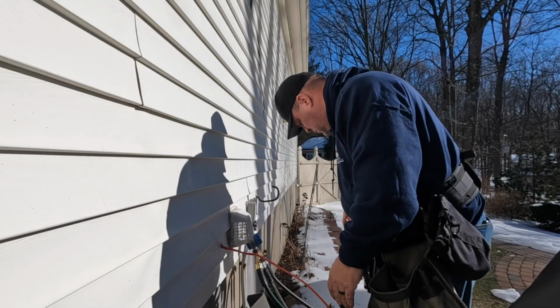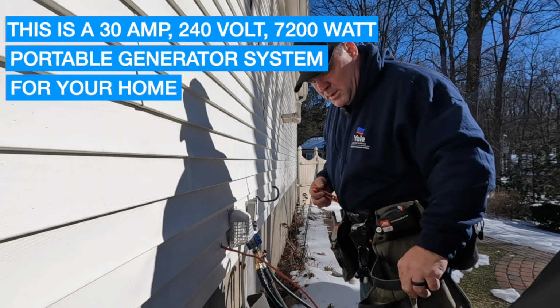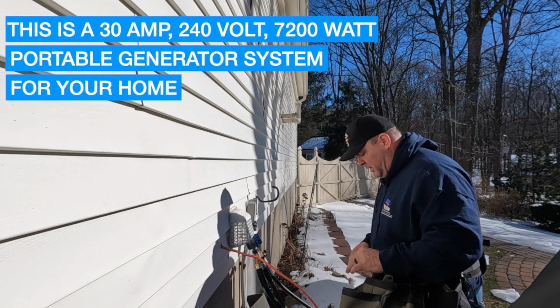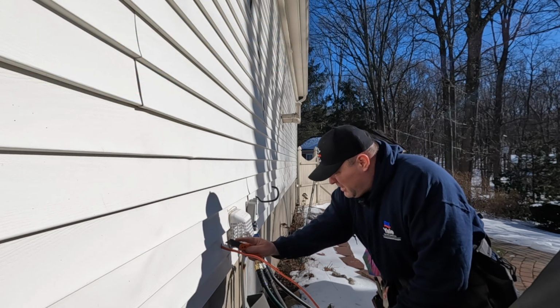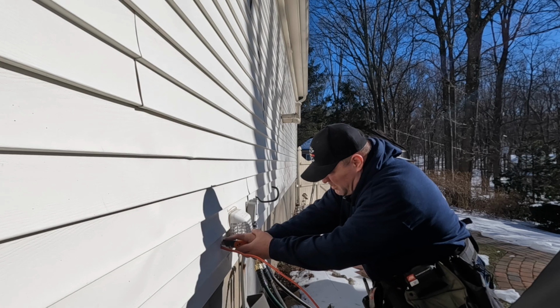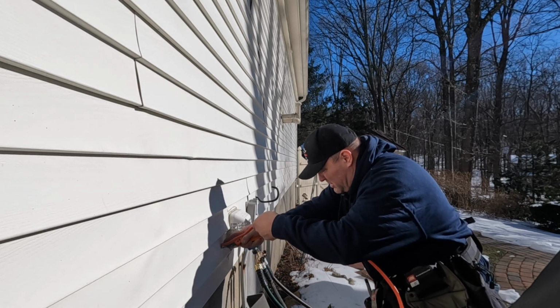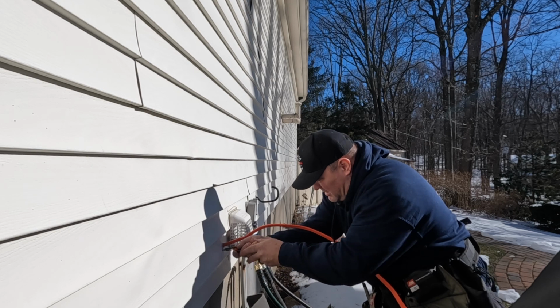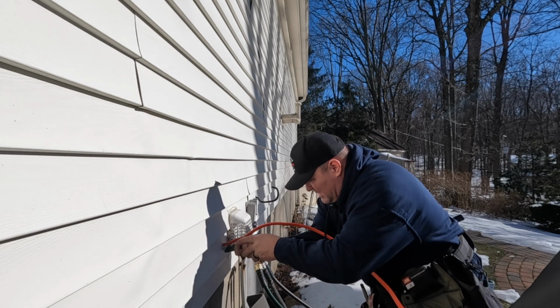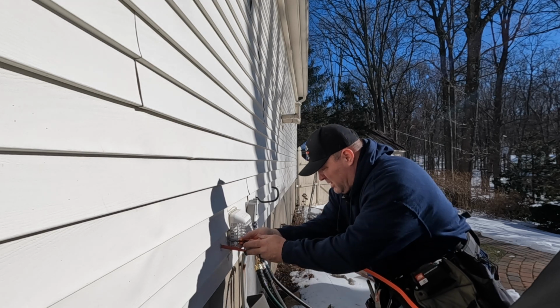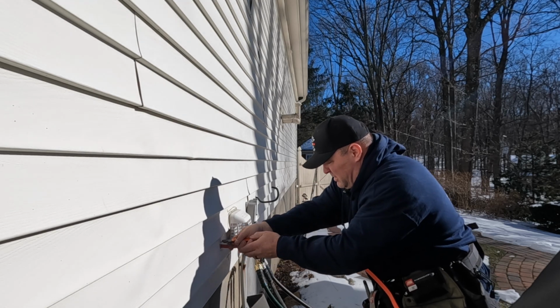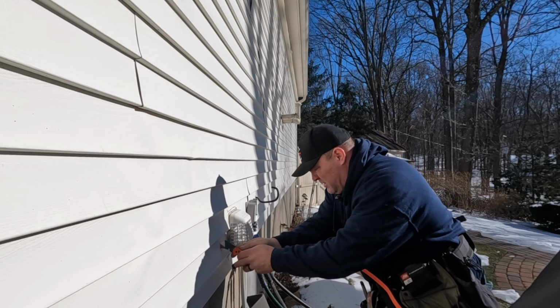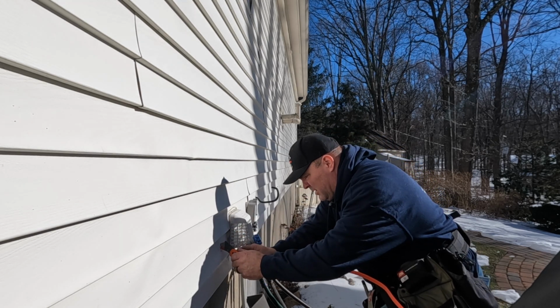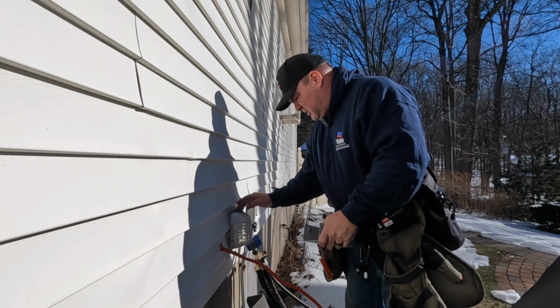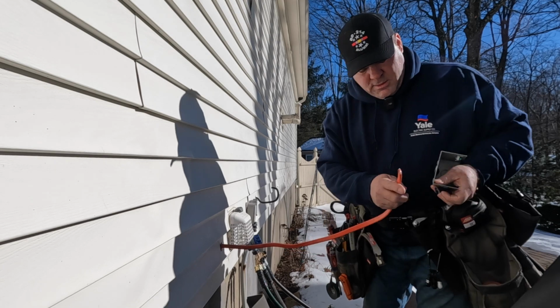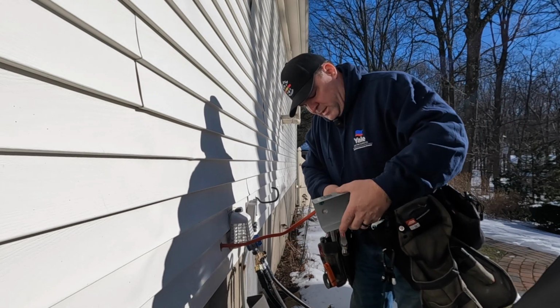Okay. All right, so the first thing I want to do is cut out so that the connector in the back of my inlet box will sit flush. So we're just going to cut out a little bit of the siding here. You probably could have done this before you ran the wire. Not a big deal though. We're just going to take out just what we need to so the thing will sit flush, or as flush as possible. We're going to caulk this up with duct seal in a moment. I'm going to set my duct seal over here for the time being, and I'm going to slide the wiring through the back of the inlet.